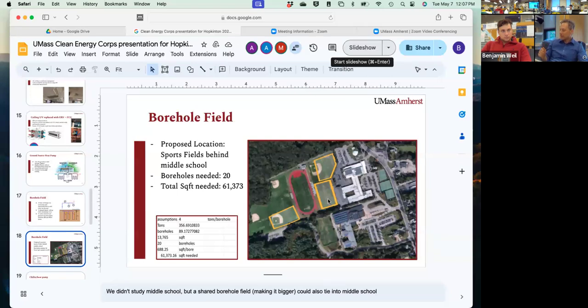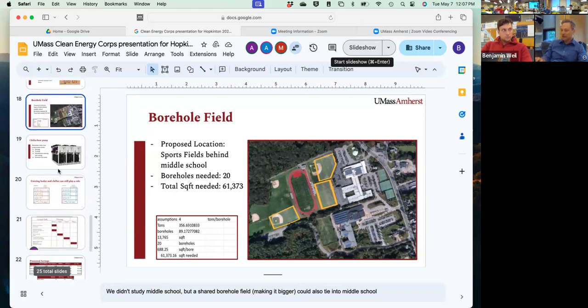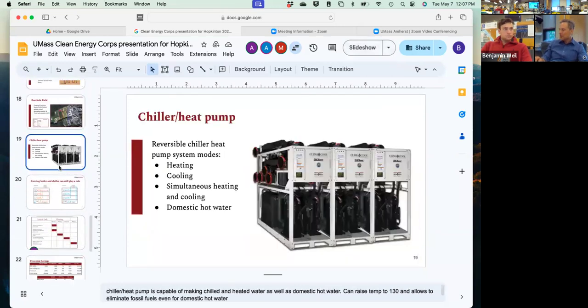The upside to sharing is there's going to be hours when the high school needs cooling and the middle school needs heating. And if you use a tri-generation chiller like this one, you're actually taking heat out of the high school, and instead of putting it in the ground, you're just putting it directly into the middle school. So at that point, you're getting, say, 700% efficiency, because you're basically doing two things that you want to do, but with one input of electricity.